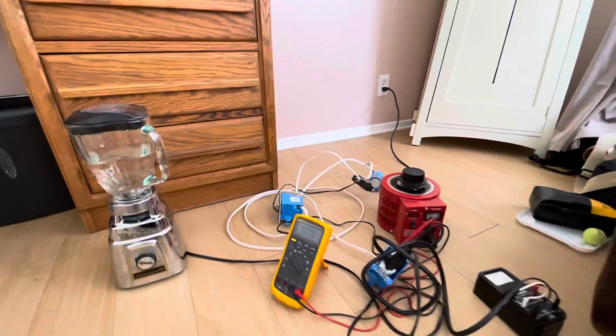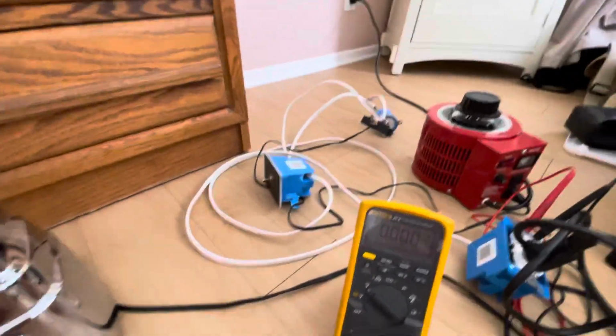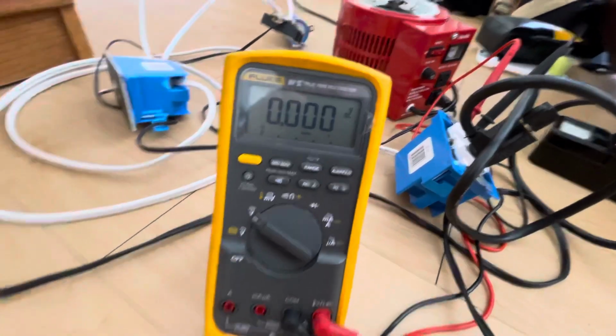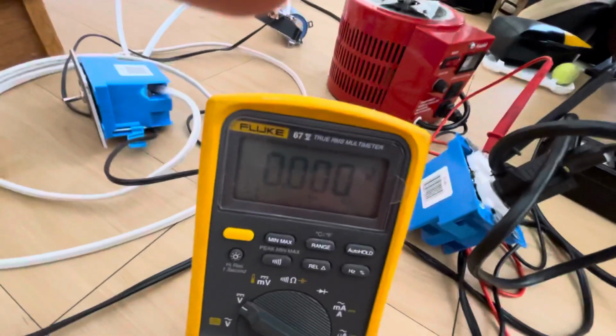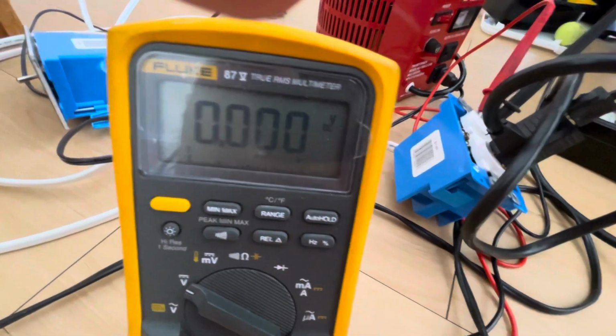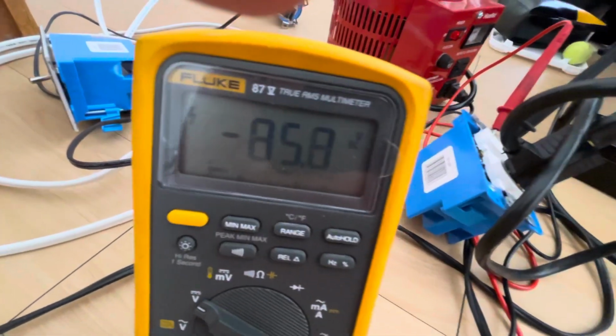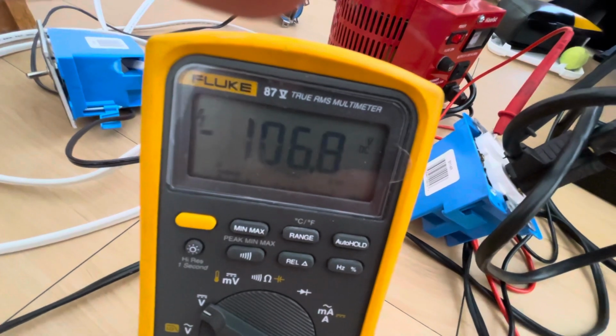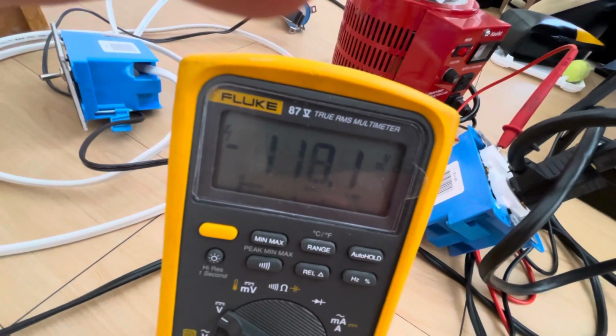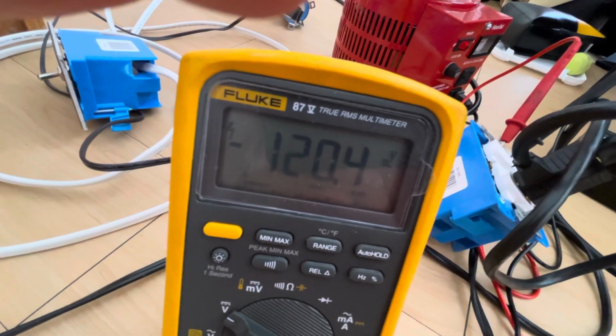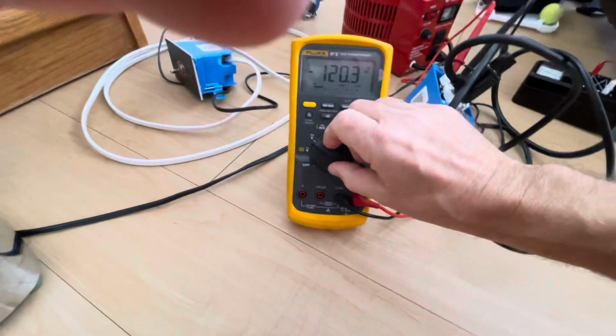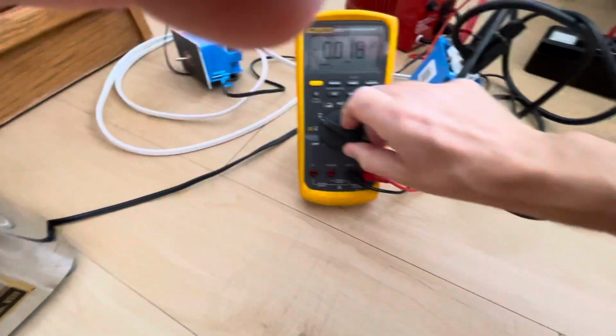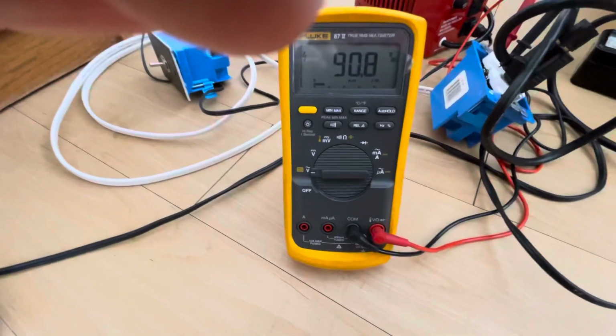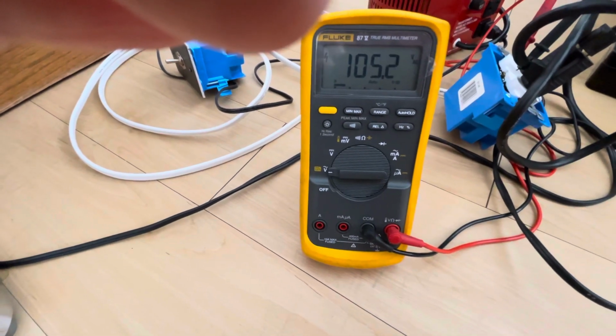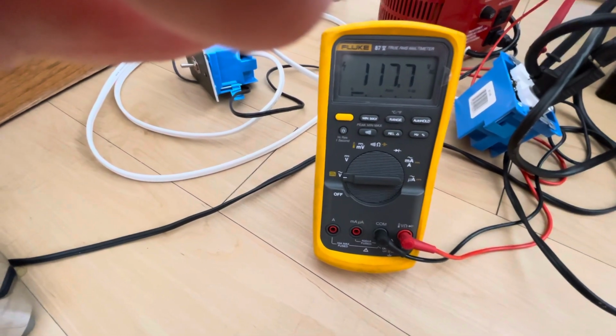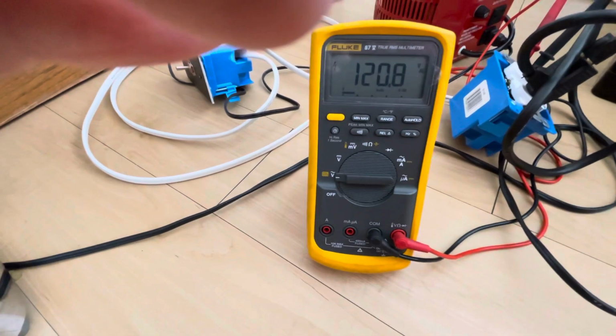Let's do one more test with 120 volts DC versus AC, see what happens. On direct current, we're going to go to 120 volts. Now I'm going to switch down to alternating current. You'll notice I need to make an adjustment because it's only at 90 volts. You can probably hear it doesn't run quite as well on 120 volts AC.